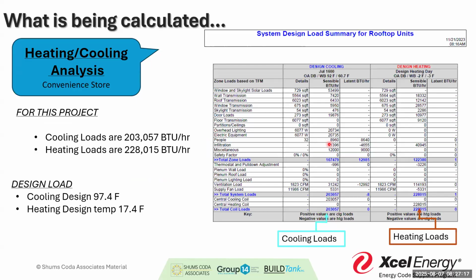But for this project in particular, we saw that the heating and cooling loads were 203 MBH and 228 MBH respectively. We can see those values at the bottom of the table. We can also see our design cooling load - we're designing for 97 and 17.